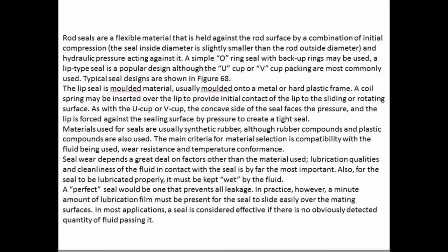A coil spring may be inserted over the lip to provide initial contact of the lip to the sliding or rotating surface. As with the U-cup or V-cup, the concave side of the seal faces the pressure and the lip is forced against the sealing surface by pressure to create a tight seal. Materials used for seals are usually synthetic rubber, although rubber compounds and plastic compounds are also used. The main criteria for material selection are compatibility with the fluid being used, wear resistance, and temperature conformance. Seal wear depends greatly on lubrication qualities and cleanliness of the fluid — the seal must be kept wet by the fluid. The perfect seal would prevent all leakage, but in practice a minute amount of lubrication film must be present for the seal to slide easily over mating surfaces. A seal is considered effective if there is no obviously detectable quantity of fluid passing.